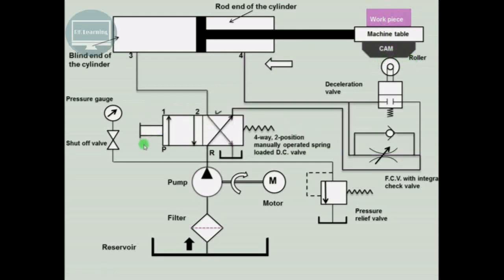When the spool of the four-way direction control valve is operated to obtain the right envelope mode, the fluid enters and travels through the check valve into port 4, causing retraction of the piston along with the machine table in the backward direction. The fluid from the other end, from port 3, goes to port 2 and then to the reservoir R.